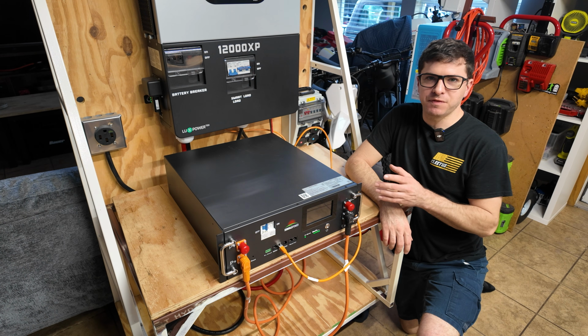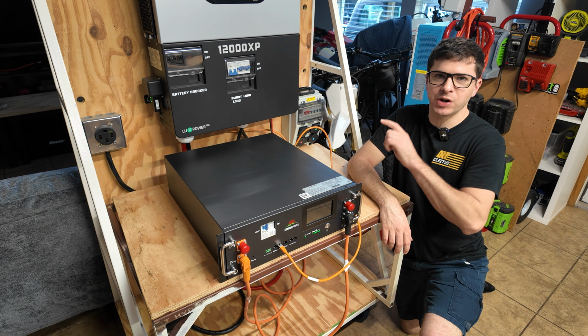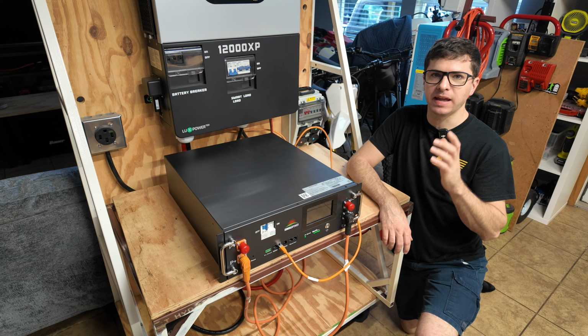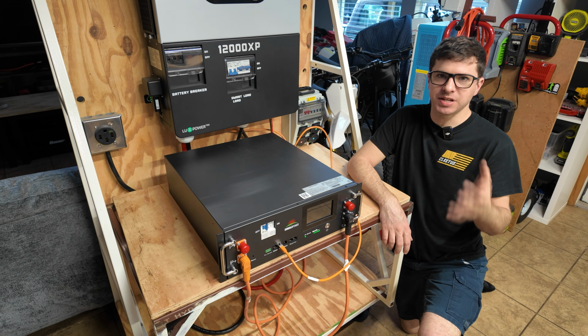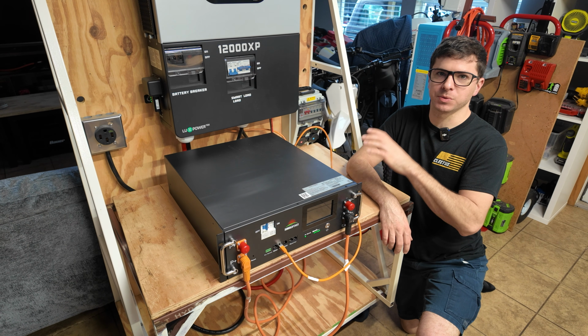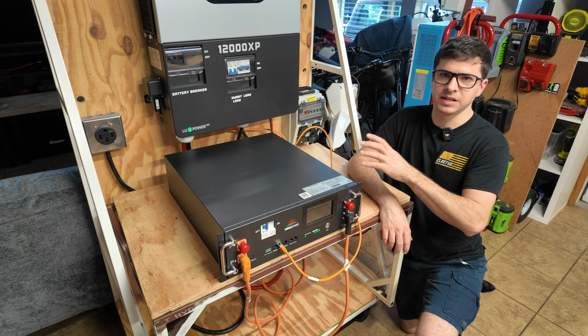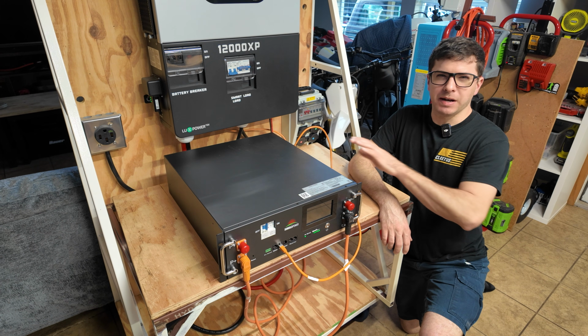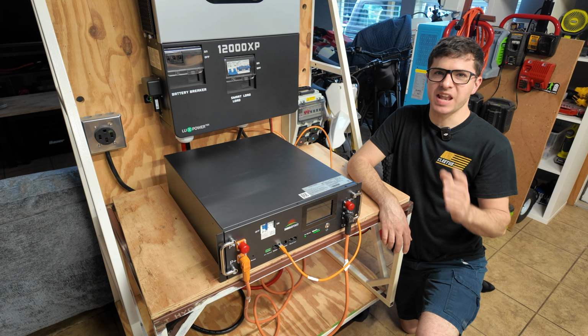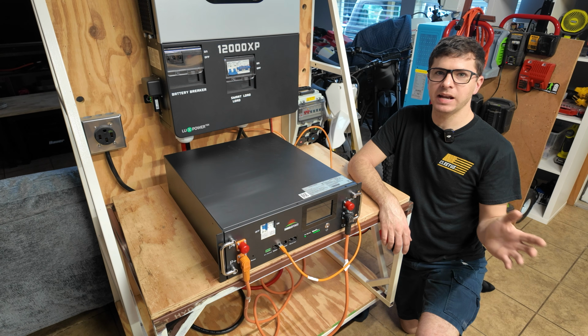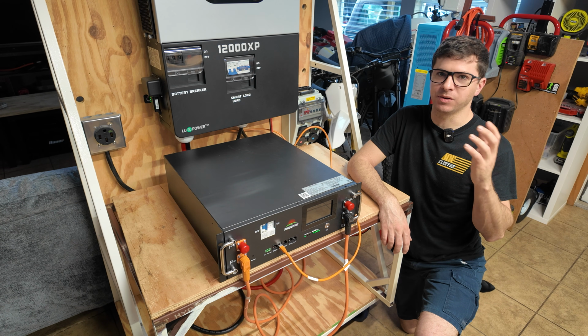How the BMS is configured according to the EG4 monitor app, it's going to allow up to 95 amps of discharge. So we're gonna push it to 95 amps and monitor the temperature with the thermal camera and just see how this thing does and how everything performs. I do believe if you had a bunch of these hooked up to your system, you would never see 95 amps out of one battery, but if they're gonna rate it at 100 amps, it's good to see that it can handle at least 95.